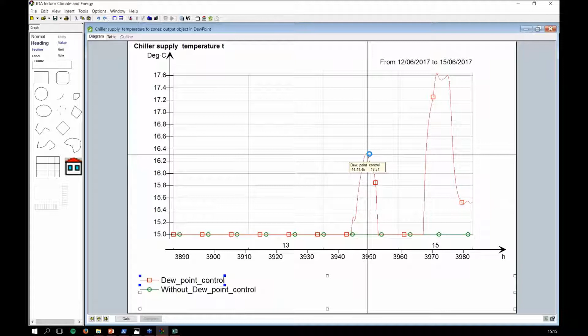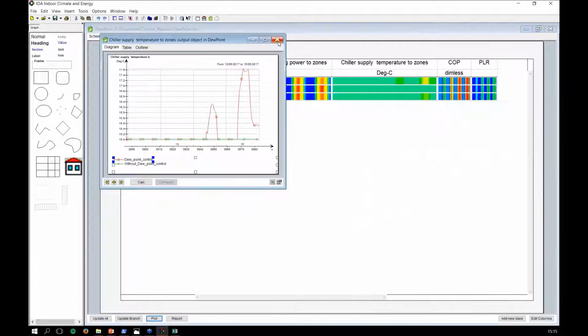So looking at this, maybe I'll zoom in there. You can see that the one without the dew point control is in green, and it keeps the supply temperature steady at 15. However, the one with dew point control, the first 2 days, I'm simulating 3 days, again in June from 12th to 15th. The first 2 days, it's keeping at 15. Probably the humidity ratio is pretty low. And then when the humidity ratio inside the building goes up, it's increasing 1 degree above that humidity ratio. So I see here the supply temperature increasing to 17.6 degrees. So my controller is working as expected. That's good news.